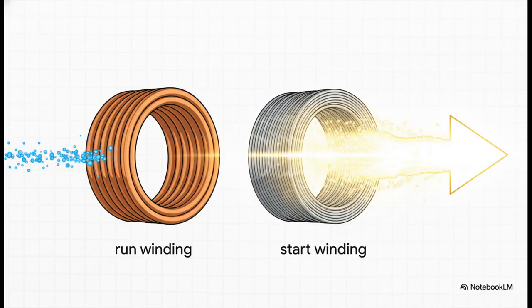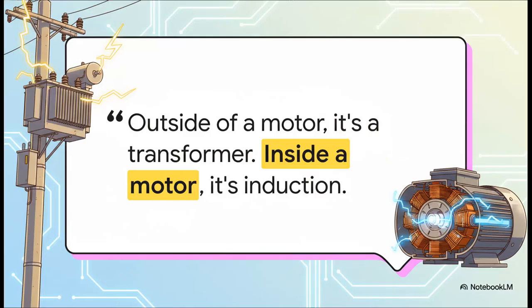And boom, there it is. That's the answer to our puzzle. Remember how the start winding is made of really long, thin wire? That means it has way more turns, or loops, than the run winding. So when that back EMF from the run winding gets induced onto the start winding, the voltage gets amplified. It gets stepped up. The motor's own design creates a hidden, built-in, step-up transformer. There's a great saying that just sums this all up perfectly. It's the exact same physical principle that makes that big transformer on a utility pole work. The only difference here is that it's all happening between two coils packed tightly inside a motor.